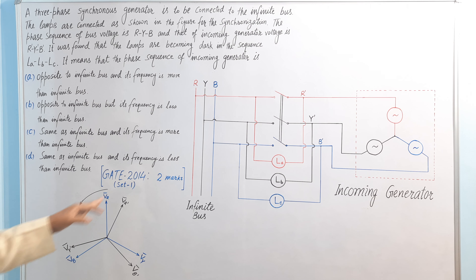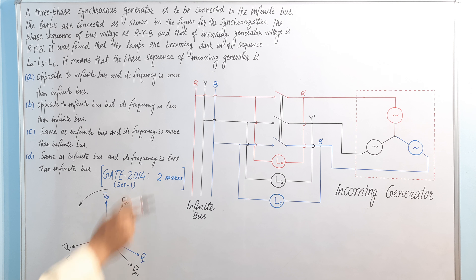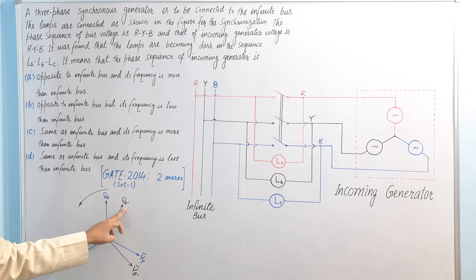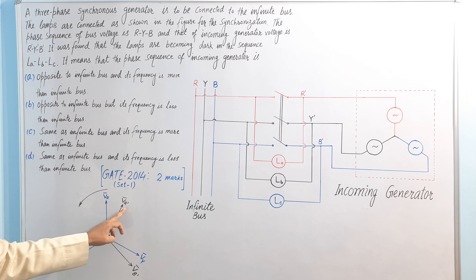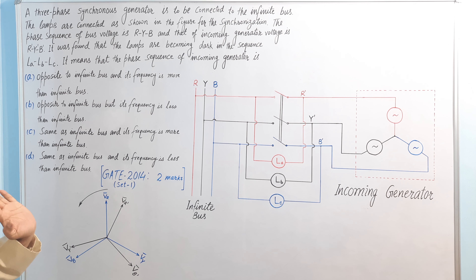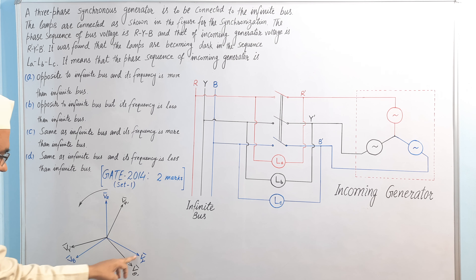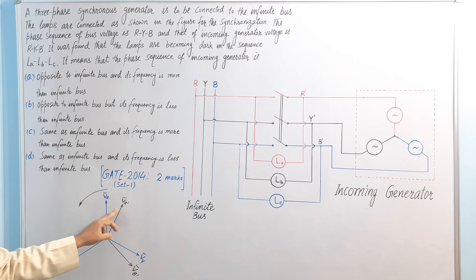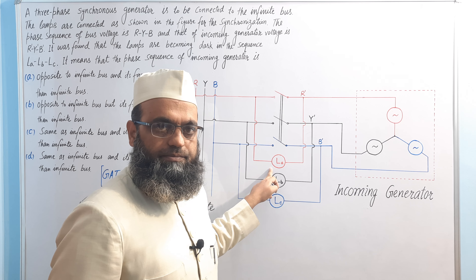The phase sequence of the incoming generator is drawn opposite to RYB. For the infinite bus it is RYB, but for the incoming generator this is R-dash, B-dash, Y-dash — not R-dash, Y-dash, B-dash. So opposite to RYB, this is R-dash, B-dash, Y-dash. If option one is correct, this phasor will cross the other at the same time — when Vr-dash coincides with Vr, lamp La will be dark, meaning voltage drop across those two points will be zero.